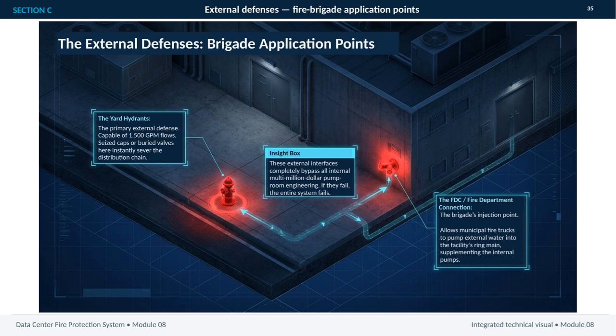This is the brigade's injection point into the facility. Municipal fire trucks can connect here and pump external water into the facility's ring main, supplementing the internal pumps and extending available support during an incident. The key lesson is that external interfaces can bypass all of the internal pump room engineering. If the hydrants or the FDC fail, the entire protection system may fail, regardless of how sophisticated the equipment inside the facility is. That makes inspection, access, and operability at these connection points essential.